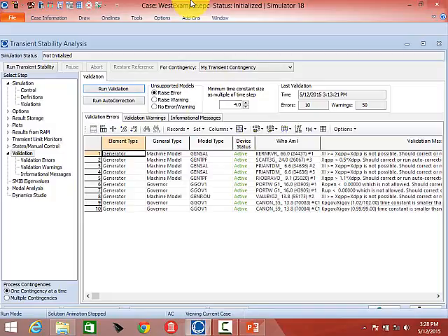So if we look at what this case picked up for, there is one where XL is too high. There's one where, another one we check is XQ double prime. If it's too different from XD double prime, that's an error.